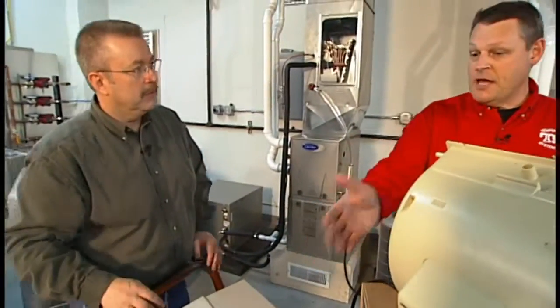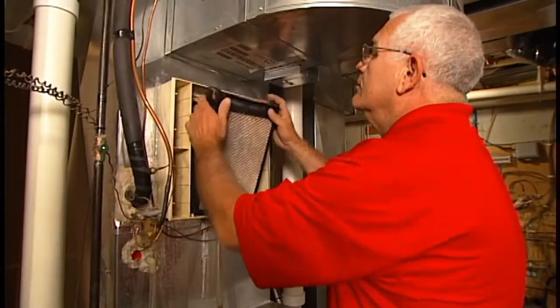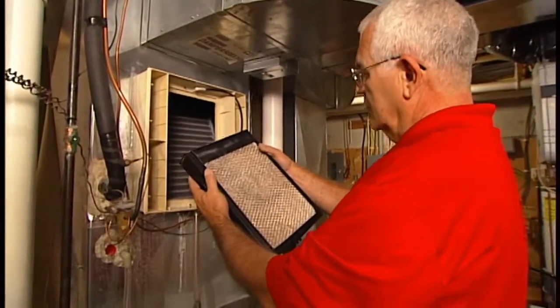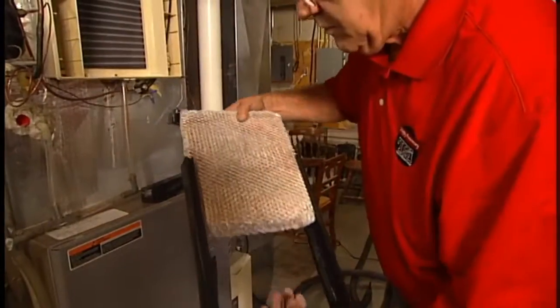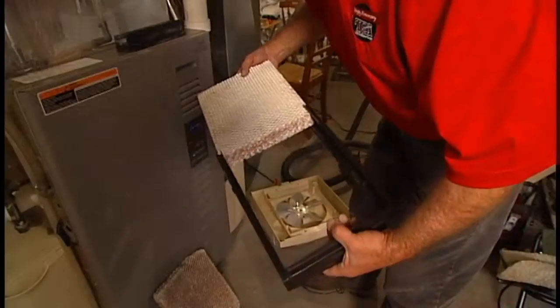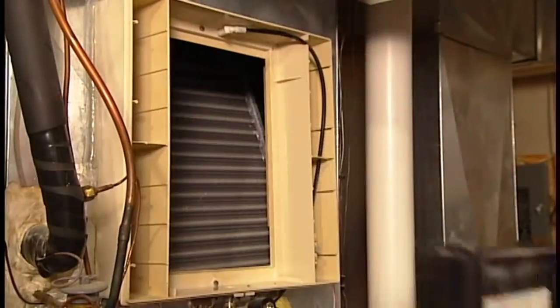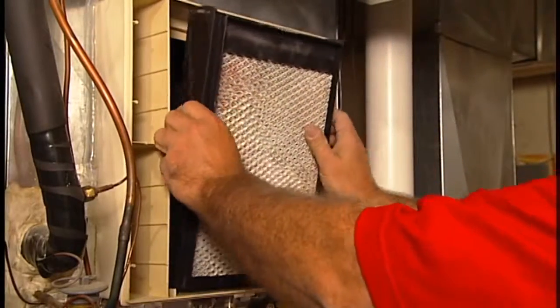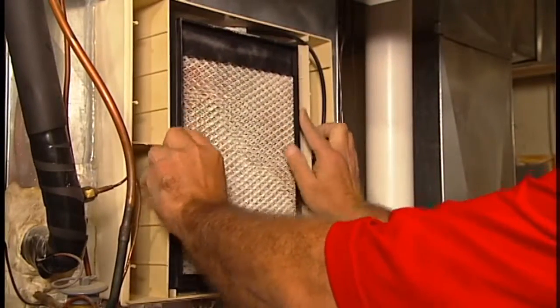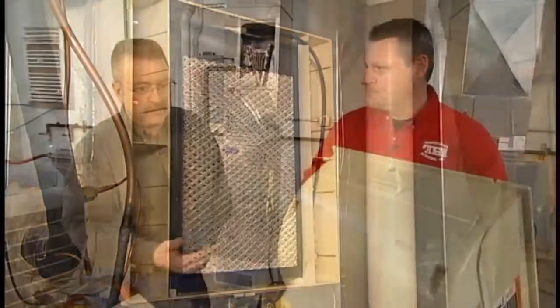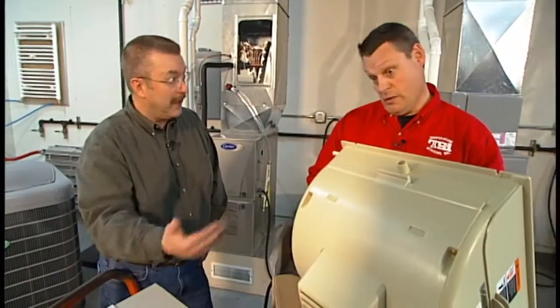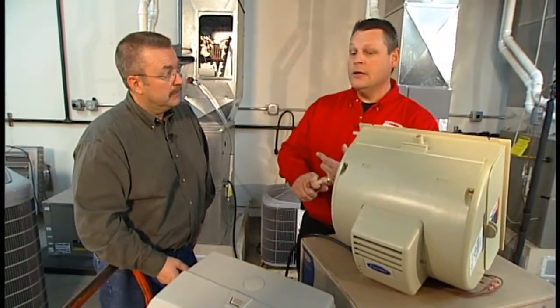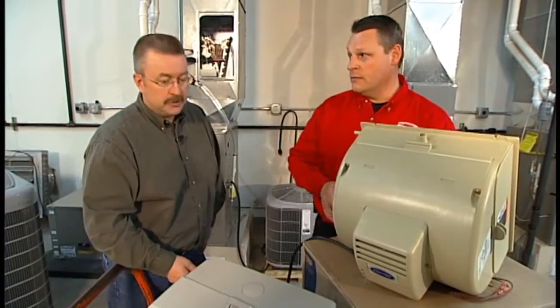Okay, once it's hooked up, anything special that the contractor or the homeowner needs to be aware of? Big thing is that pad we just looked at, that is going to be a maintenance item where annually is typical replacement intervals for that. So once a year, plop in a new one. What will happen is the hard water deposits will eventually collect on that to where it's inoperable. Then it needs to be replaced. The amount of hardness in their water determines how much they're going to actually have to replace that. Yeah, and along those lines, probably a good idea to connect it to a water softener if you have one there. Exactly. Water softener, also tying it on to the hot water side to give you a little bit enhanced moisture vaporization taking place. Sure, makes sense to me.